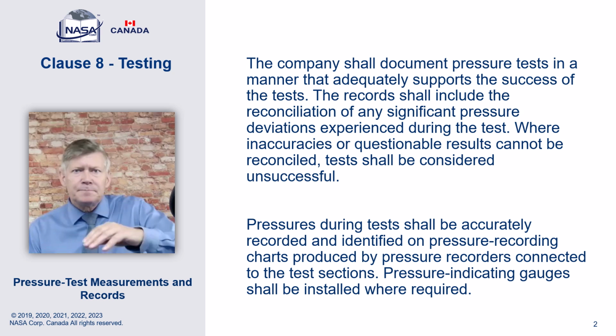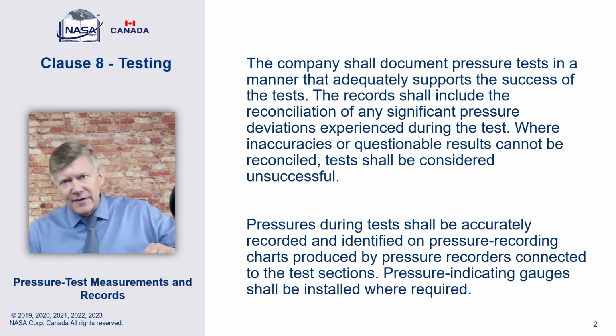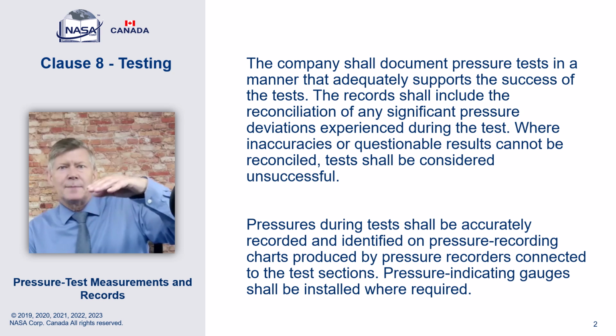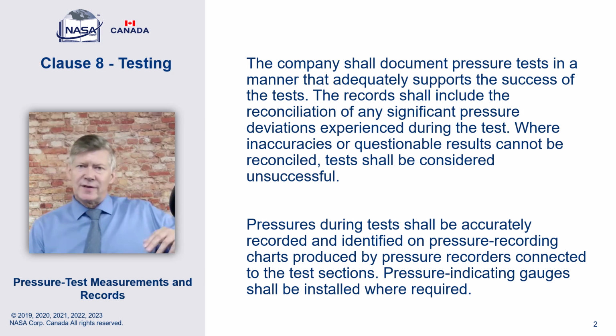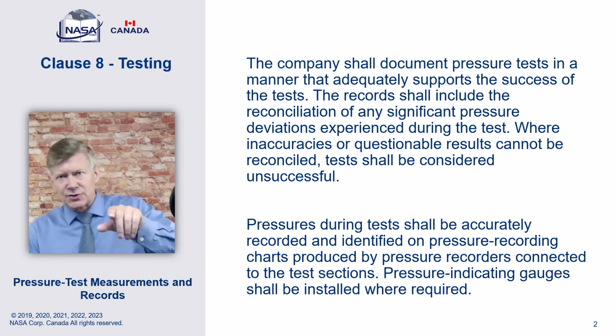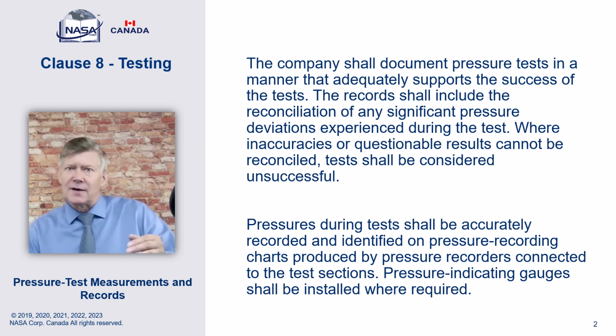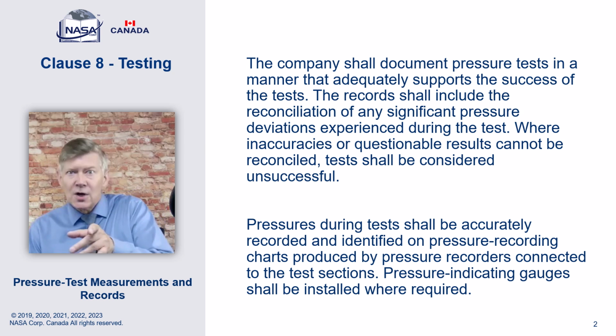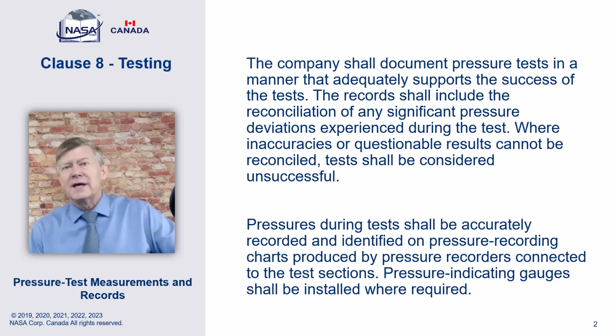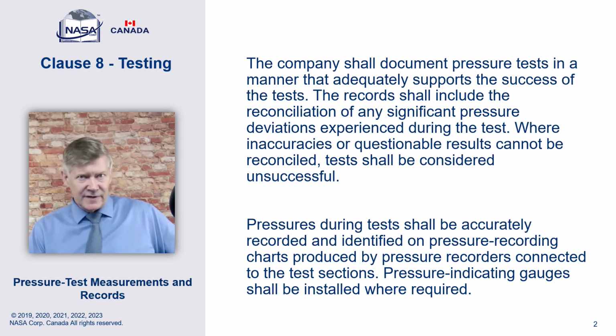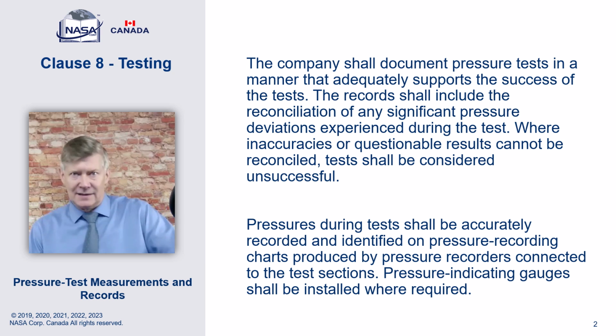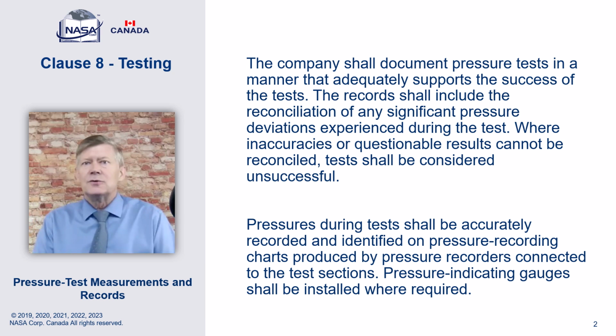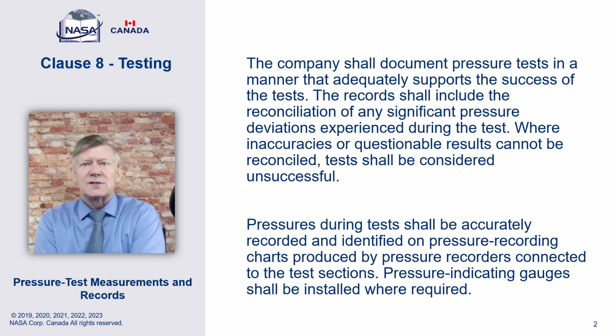This was a buried line. They minus 10 dropped to minus 20 overnight, and then when the sun came out in the morning, warmed back up to minus 5. So in theory, we should have seen a pressure drop down and come back up again. All we saw on the record was a steady and stable drop over the period of 24 hours. So again, they had done a test 3 weeks previous that showed that they had a leak. Right? And what it came down to was arguments over what constitutes a significant pressure deviation.